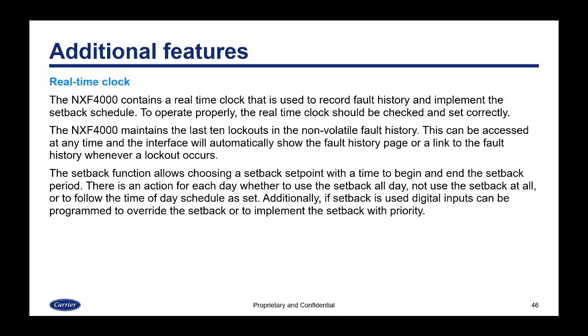The NXF4000 contains a real-time clock that is used to record fault history and implement the setback schedule. To operate properly, the real-time clock should be checked and set correctly periodically. The NXF4000 maintains the last 10 lockouts in the non-volatile fault history, and this can be accessed at any time, and the interface will automatically show the fault history page or a link to the fault history whenever a lockout occurs.